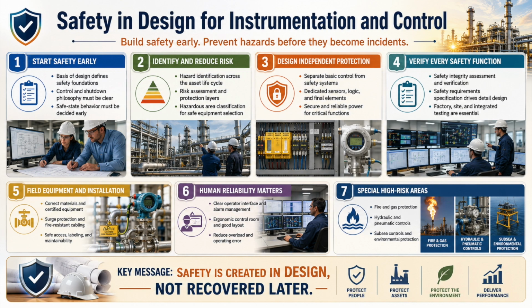A supplier may offer a proven standard panel, but proven elsewhere does not mean compliant here. Local legislation, hazardous area requirements, ambient conditions, certification, required safety performance, alarm philosophy, communications behavior, and failure action must all be verified. Historical design is not a substitute for current compliance.